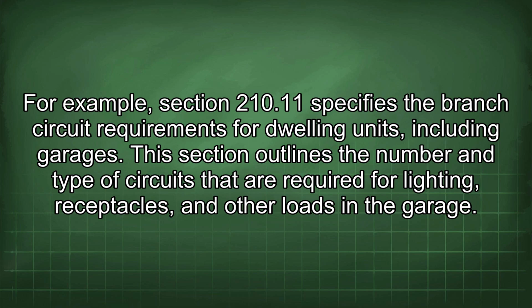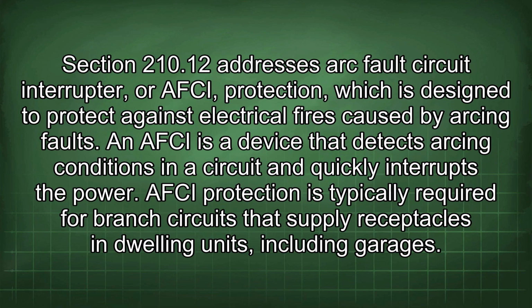including garages. This section outlines the number and type of circuits that are required for lighting, receptacles, and other loads in the garage. Section 210.12 addresses arc fault circuit interrupter, or AFCI, protection, which is designed to protect against electrical fires caused by arcing faults. An AFCI is a device that detects arcing conditions in a circuit and quickly interrupts the power. AFCI protection is typically required for branch circuits that supply receptacles in dwelling units, including garages.